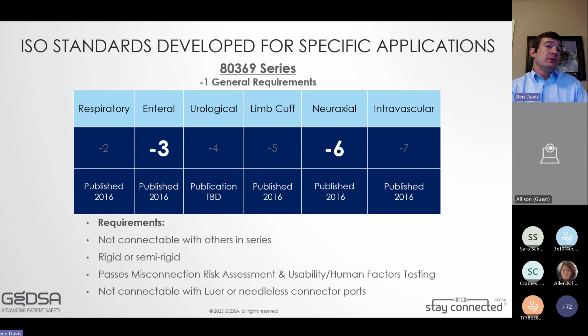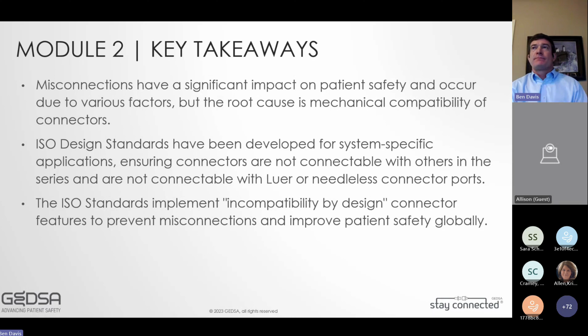So our key takeaways for that module are that misconnections have a significant impact on patient safety, and they can occur due to various factors, but the root cause really is the mechanical compatibility of connectors. ISO design standards have been developed for system-specific applications, ensuring that connectors are not connectable with others in the series and are not connectable with Luer or needleless connector ports. The ISO standards implement incompatibility-by-design connector features to prevent misconnections and improve patient safety. So basically, through this series of standards, each application has a dedicated set of connectors that does not work with any of the other applications.